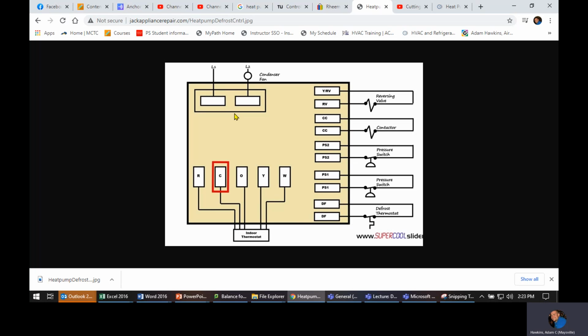The warmer it gets, the faster it defrosts, the faster it thaws, the faster we go back to heating. So we're running this thing in cooling. So now your indoor unit becomes your evaporator. Your blower inside is still running because it has to run or your indoor unit would freeze up. So you're blowing cooling into your house. You don't want to do that forever, obviously, because you're trying to heat this place.